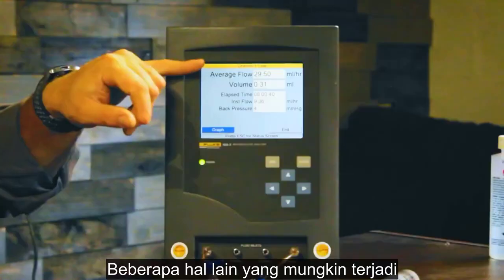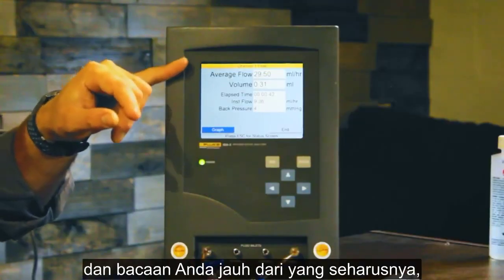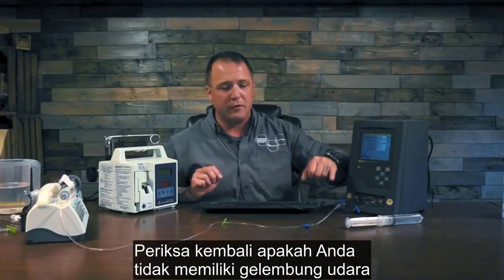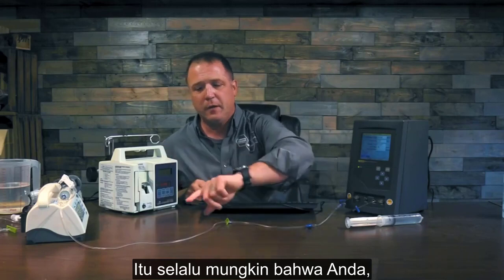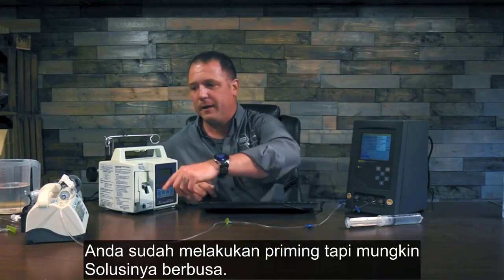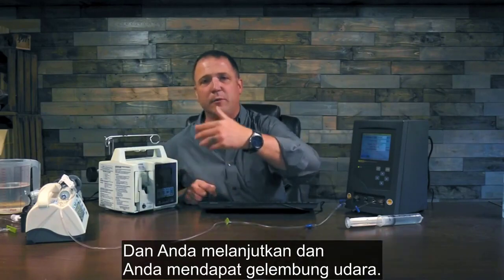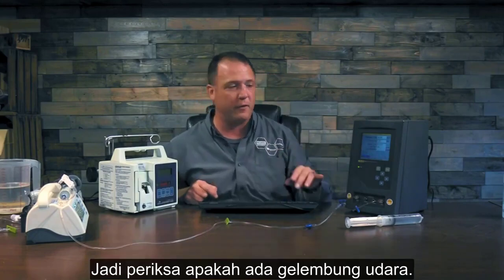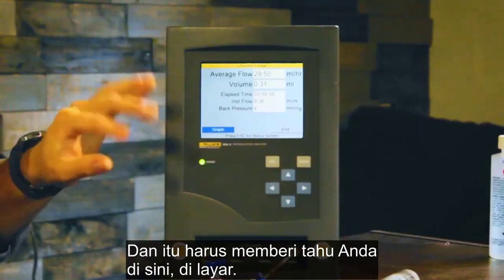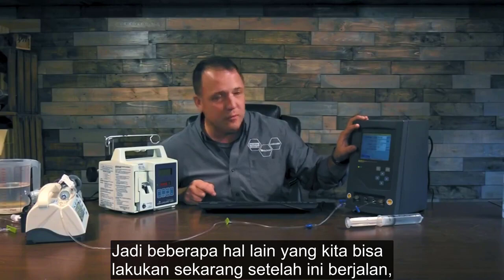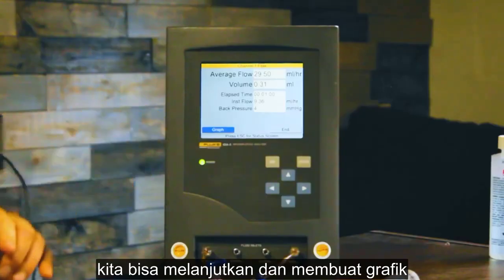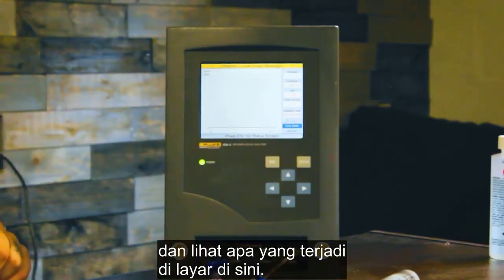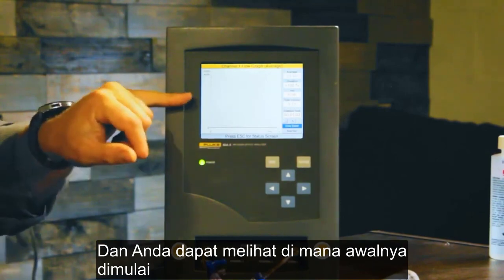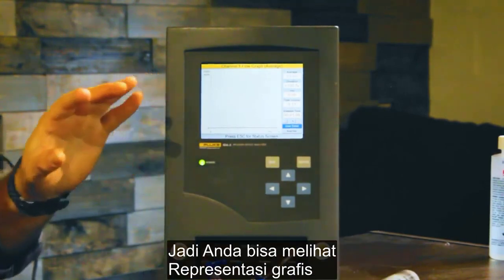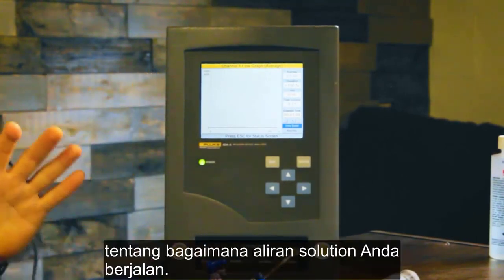Some other things that might happen is if you get done at the end of your test and your readings are way off, double check that you didn't have any air bubbles in your line. That's always possible, that you primed it, but maybe the solution was foamy and you got an air bubble. So check for those air bubbles and it should tell you right here on the screen. So some other things we can do now that this is running, we can go ahead and graph it and see what's going on the screen here. And you can see where it initially started and our current flow. So you can see a graphical representation of how your flow is going.